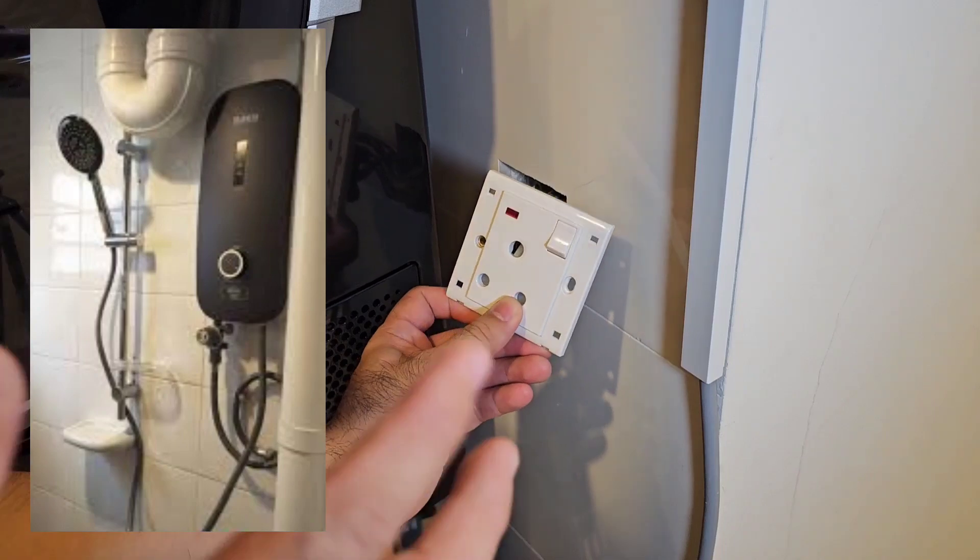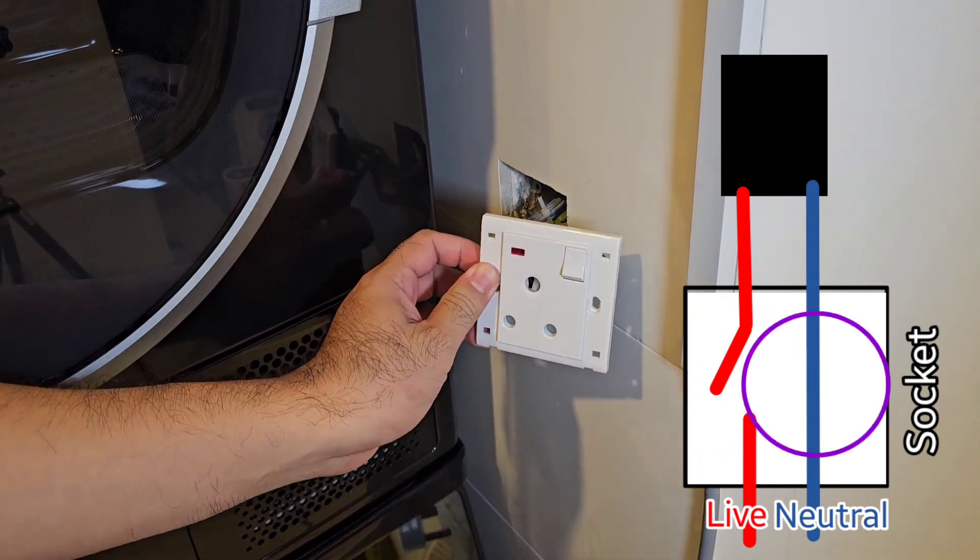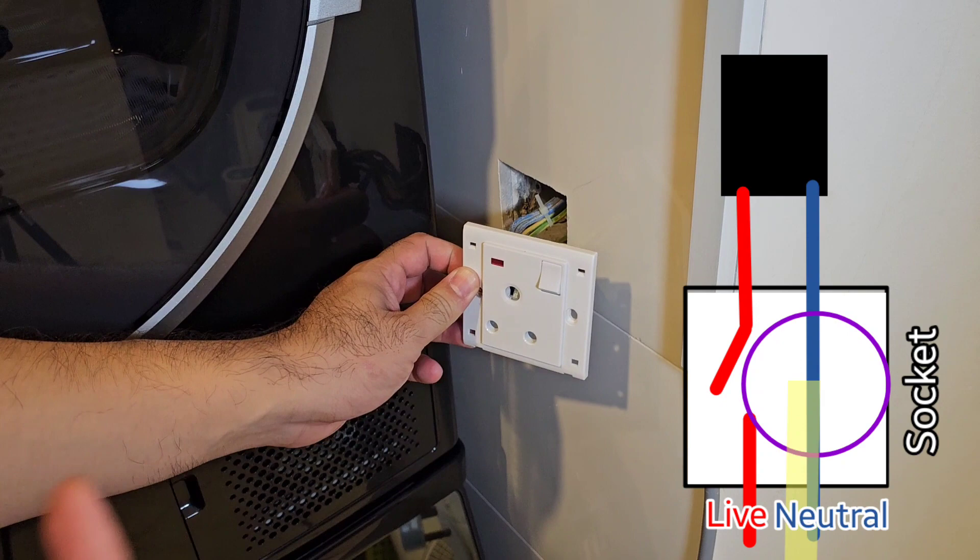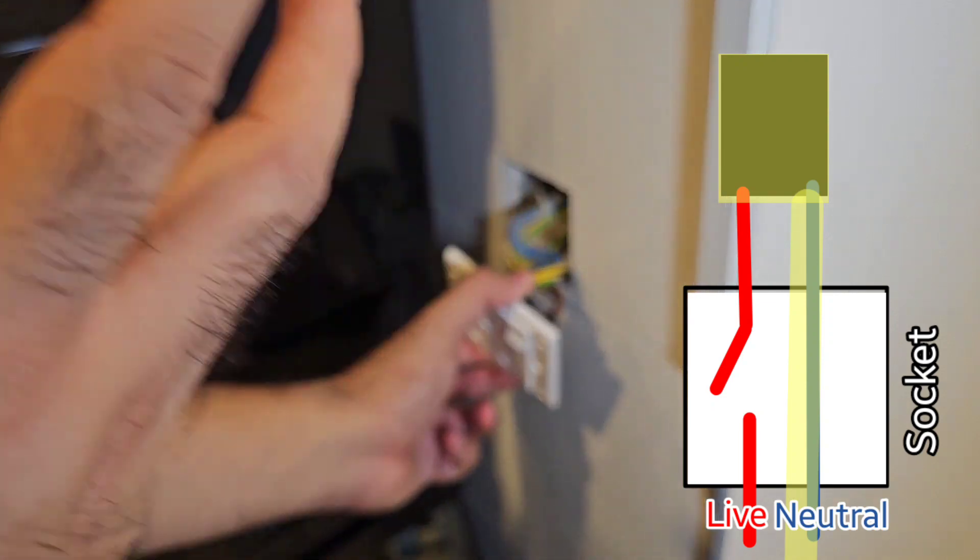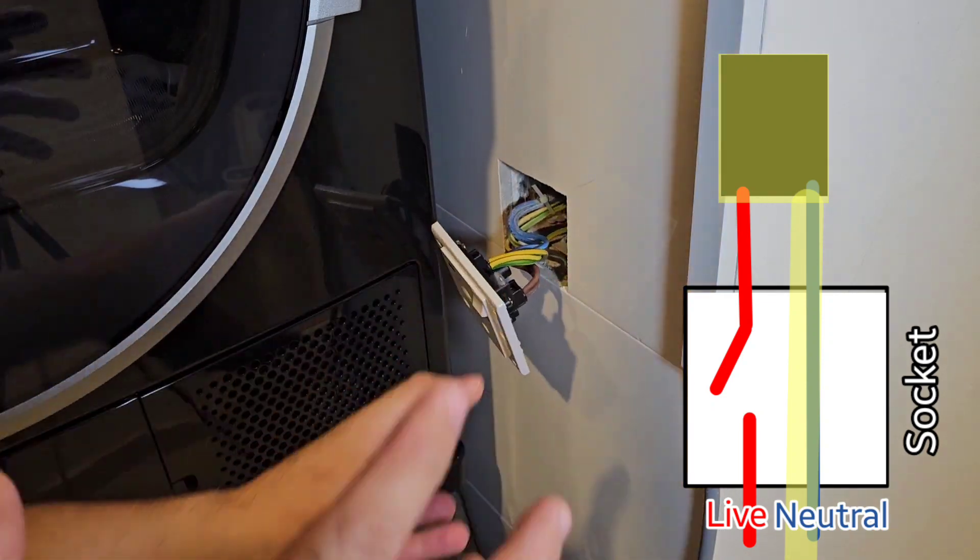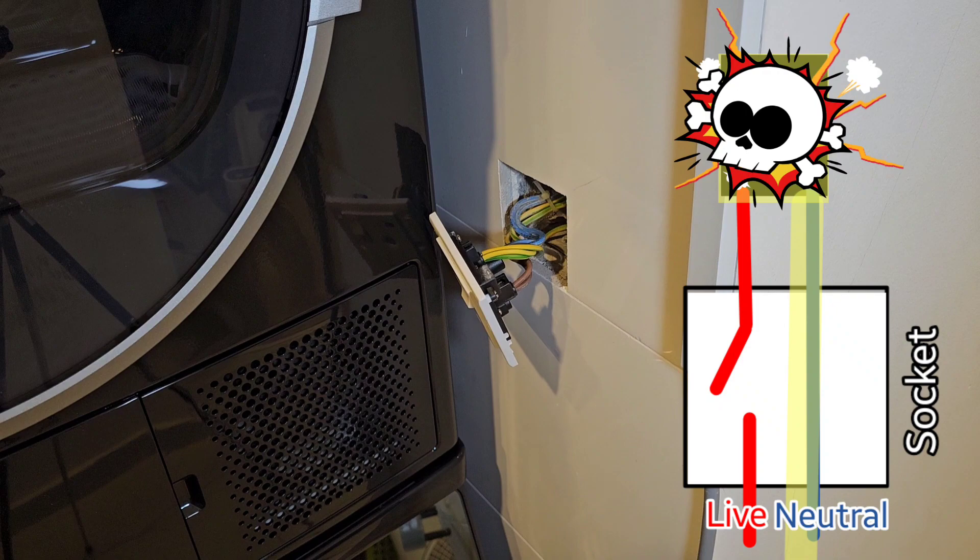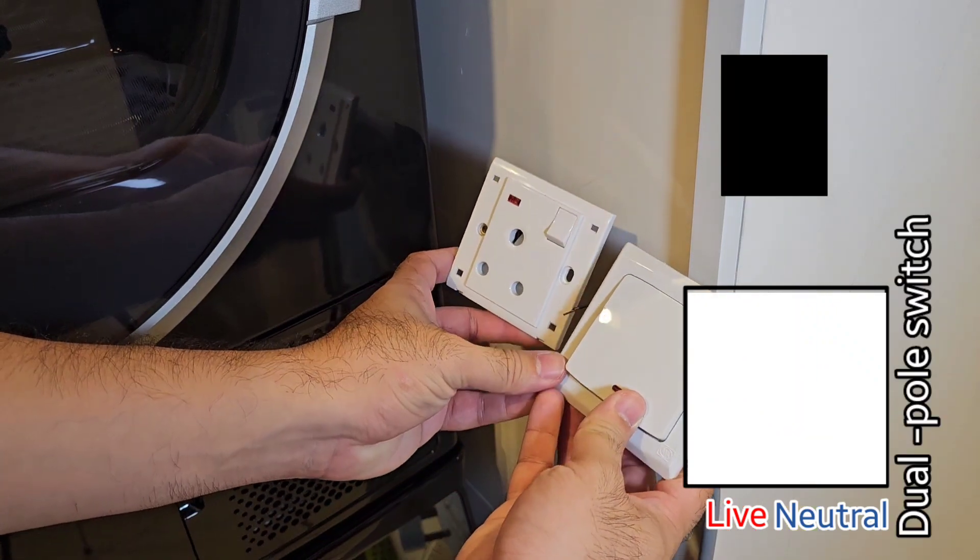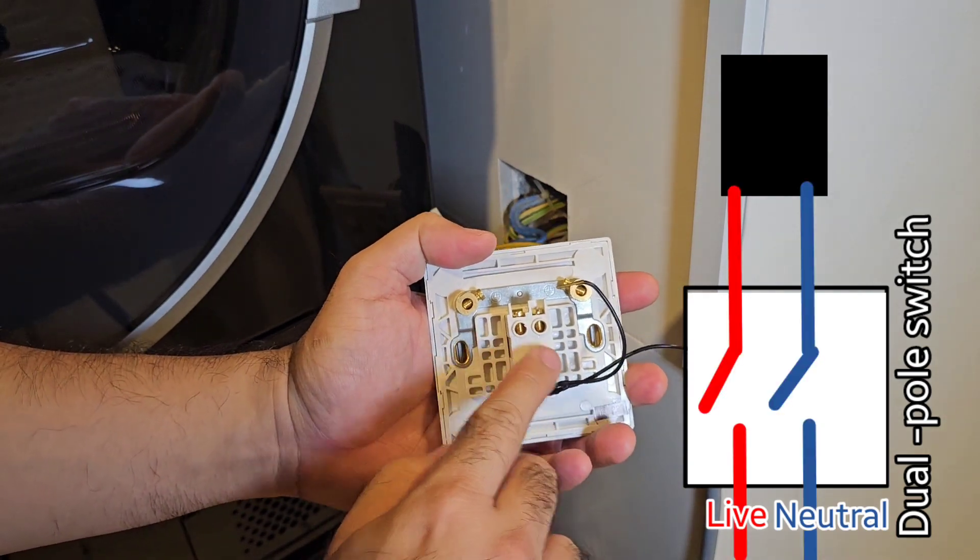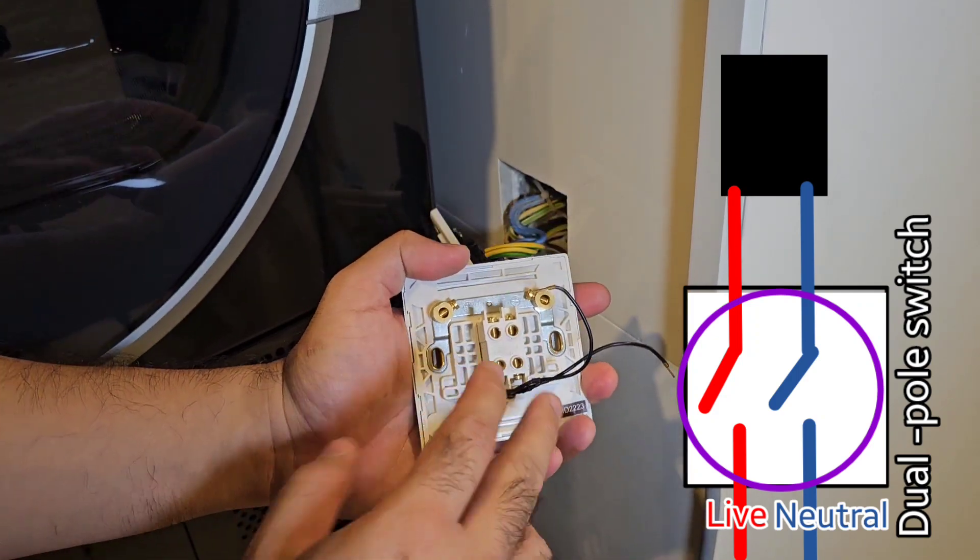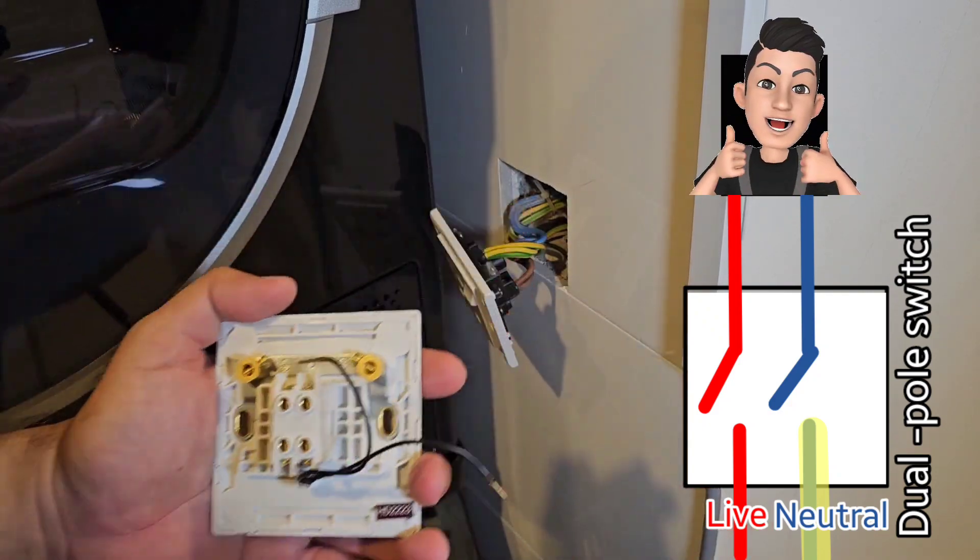So with these kind of water heaters you do not want to have a socket because a socket only controls the live and it cuts the live off. The neutral is still connected, and what happens is if your neutral is energized or there's a short somewhere, you're gonna get current flowing into your water heater. If anyone were to touch it, if the water heater is faulty, if your RCCB is faulty, they may very well end up hurting themselves. So the best thing to do is to change this into a dual pole switch, and what this switch actually does is breaks the contact of your live and your neutral. So if there's any fault in the circuit, your water heater is totally isolated from the house.